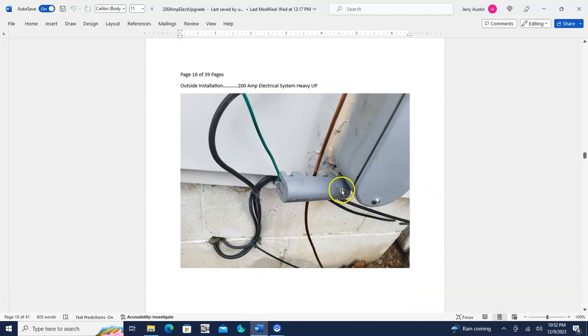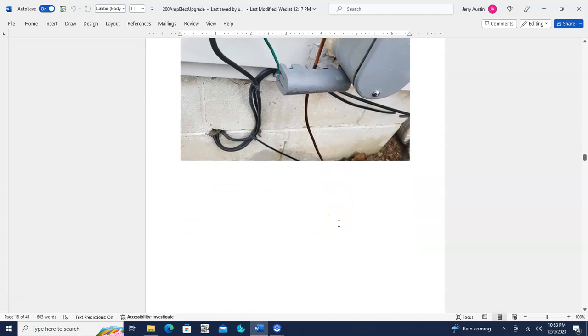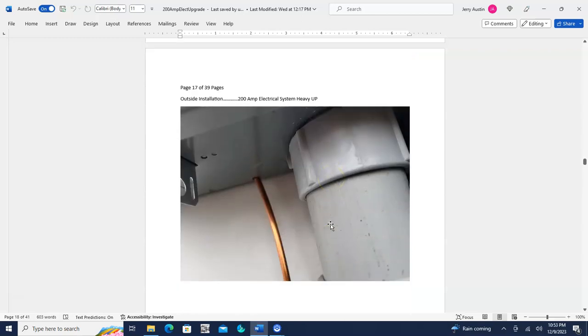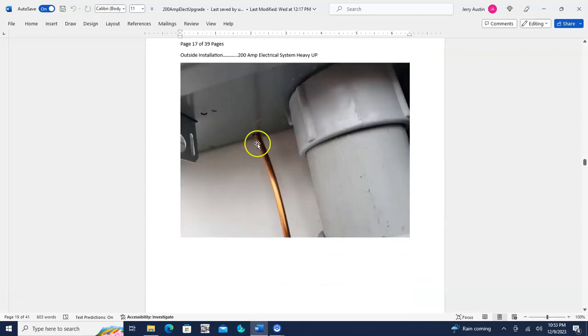This is a little connector. We've already seen this. It's a little connector here that just hooks on there, and this is for the ground rod wire coming down through there, and that's a solid copper wire. This is a close-up of that solid copper wire coming down through the quick disconnect box, and this is where the PVC hooks into the bottom of that quick disconnect box. And then you've got a little piece of PVC here, and then it hooks onto that elbow where the wires feed into the house.